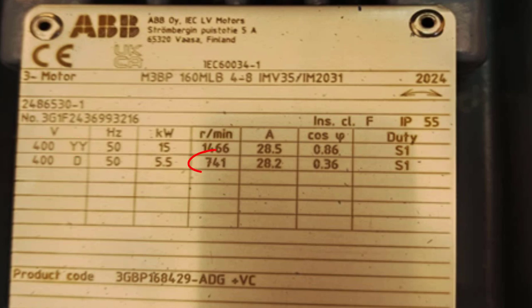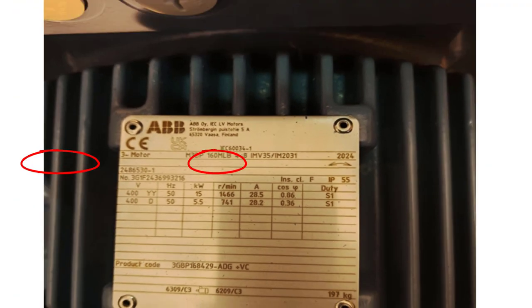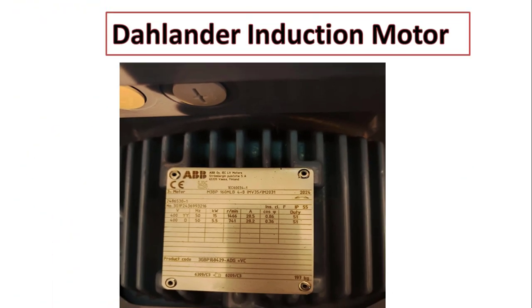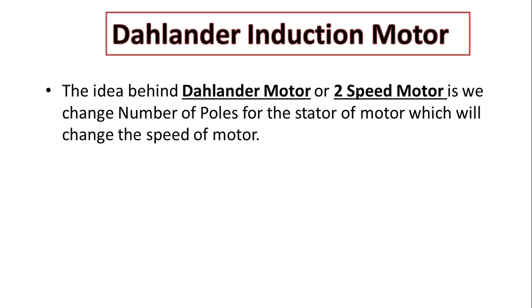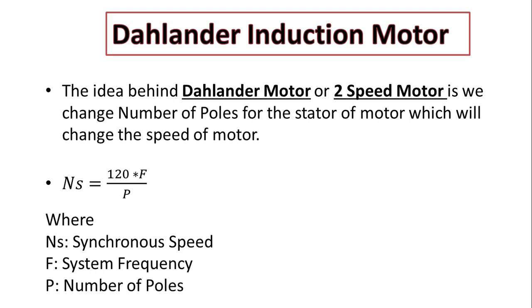Actually, the idea behind this motor is when we change the connection, we change also the number of poles in the stator of the motor. Here in this formula, as you can see, the synchronous speed Ns is equal to 120 times the frequency over number of poles.